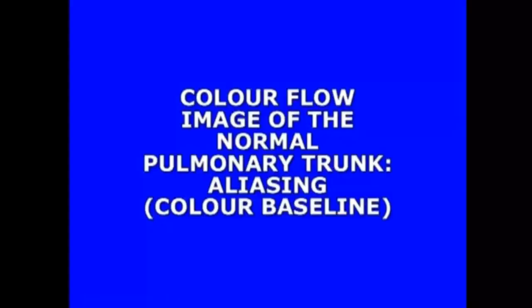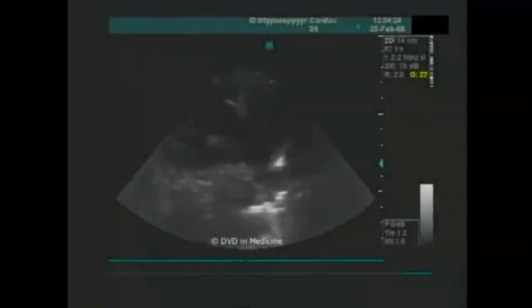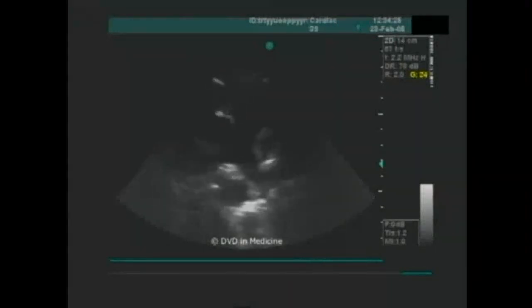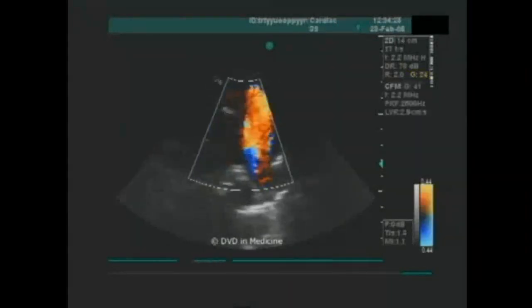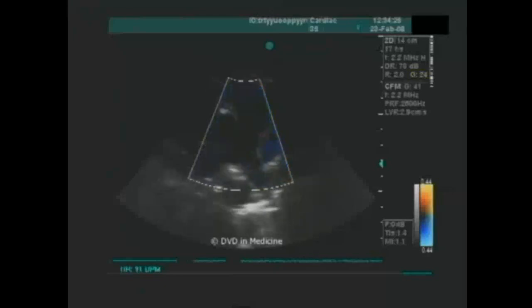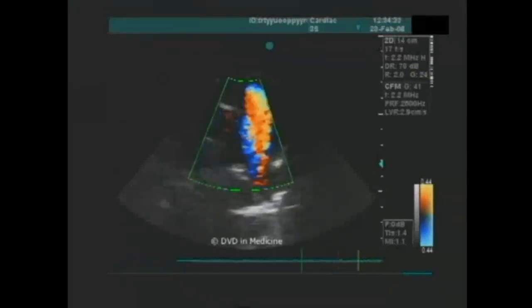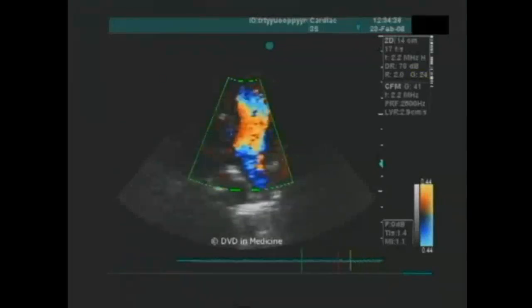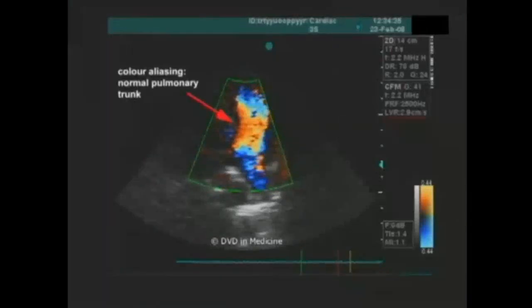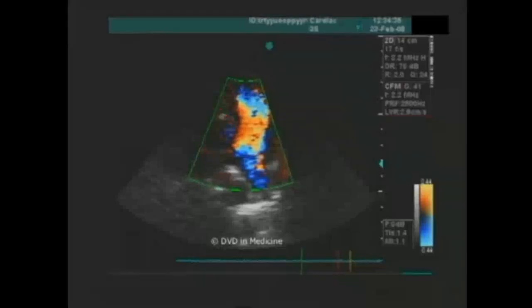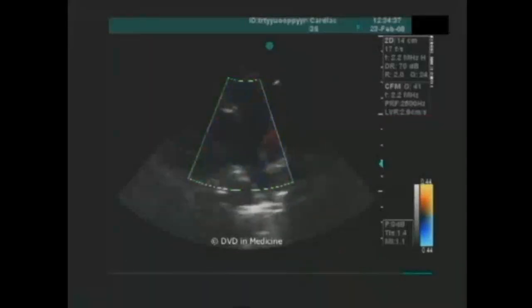Color flow image of the normal pulmonary trunk. Aliasing, adjusting the color baseline. By shifting the color baseline, one increases the velocity limits in the direction away from the transducer, but at the expense of the velocities in the opposite direction.